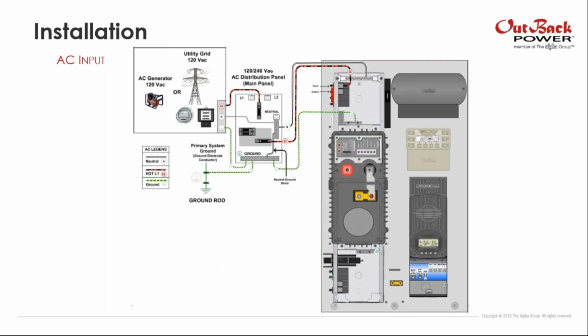For the AC input, if you have an AC generator or you're going to use the utility grid for the AC input, everything you will need is to identify the input breaker, which will be at the top of the FLEXware, and to connect from the main panel to the input breaker. The neutral comes from one bus bar to another one. That's exactly the same, and same case for the ground. And that's it.